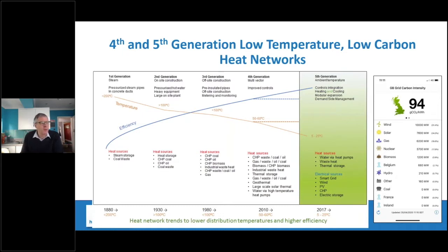It's pretty common now for a lot of new heat networks to be designed around 70-degree flow temperature, for example, or even lower. And we're now starting to see very low temperature systems, ambient loop systems as we call them, where the temperatures are between 5 and 20 degrees, with local boosting of those temperatures in the buildings using heat pumps. So we're on this low carbon journey, and I think low carbon heat networks are certainly going to have a big part to play in future heat strategy in the UK.